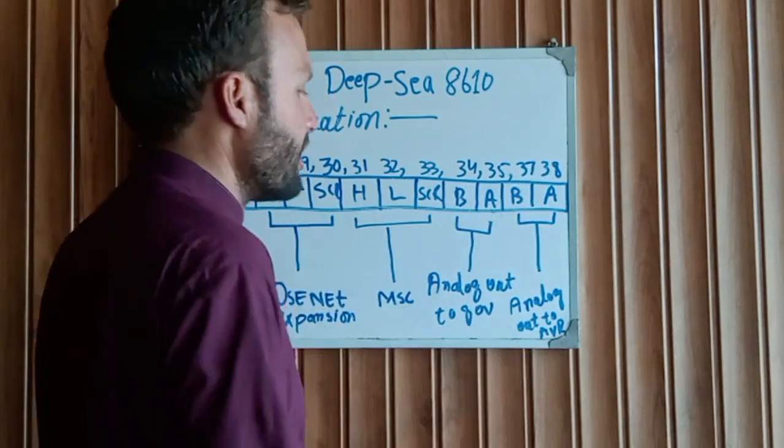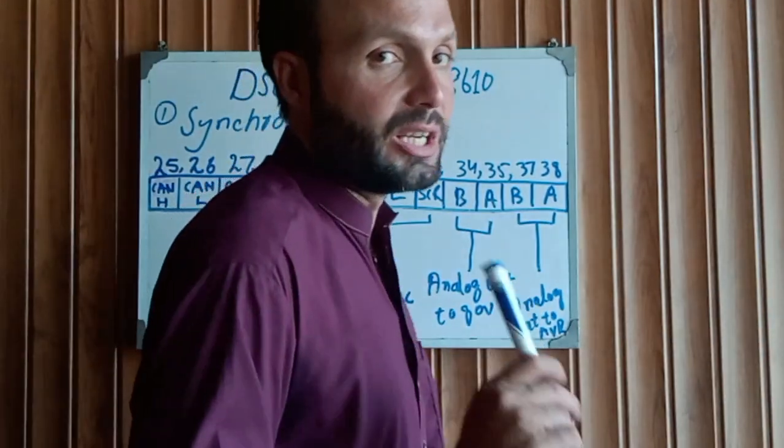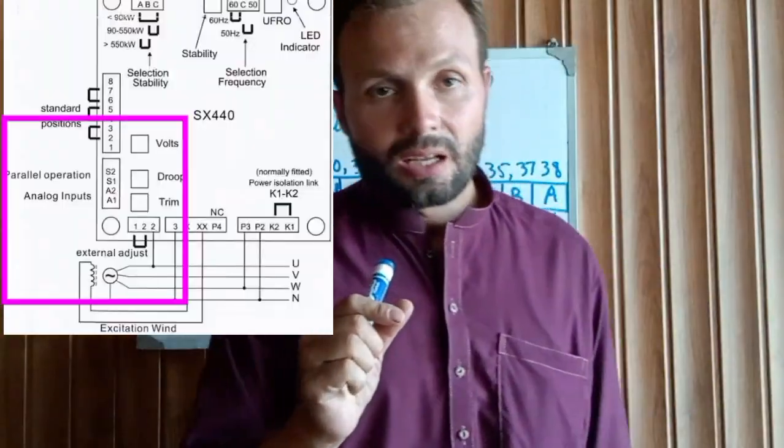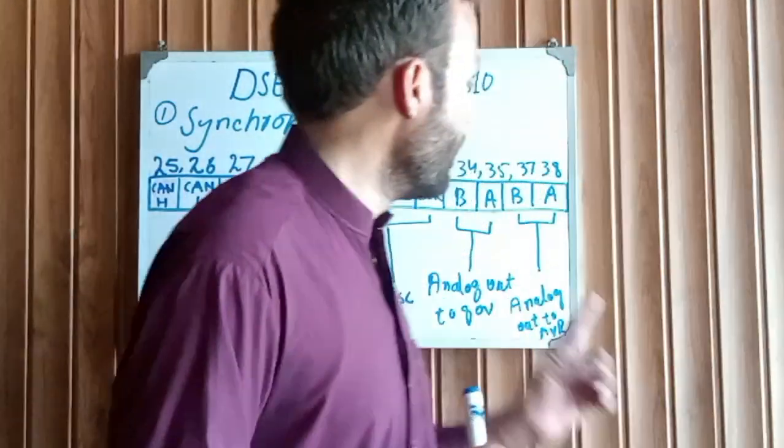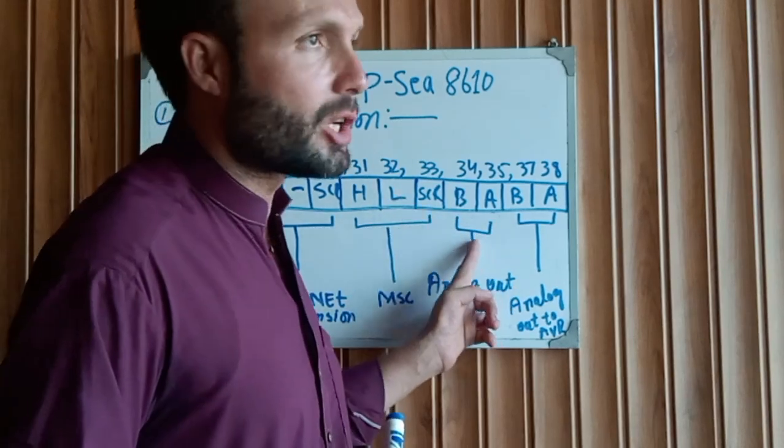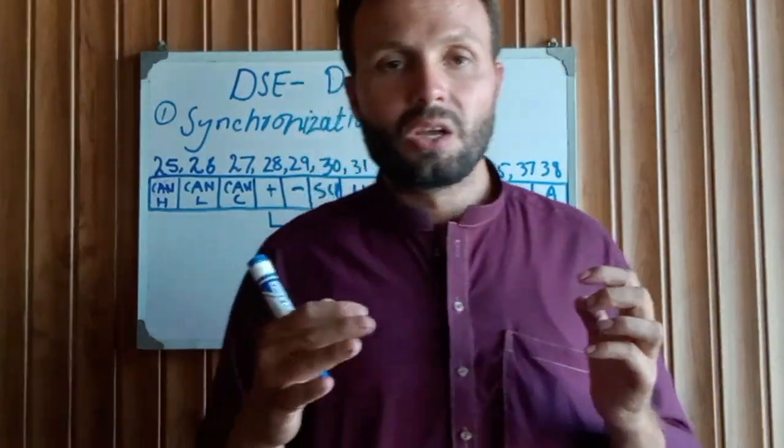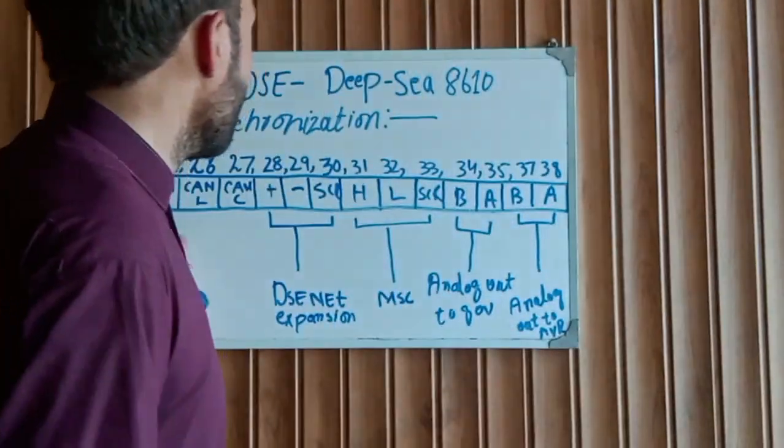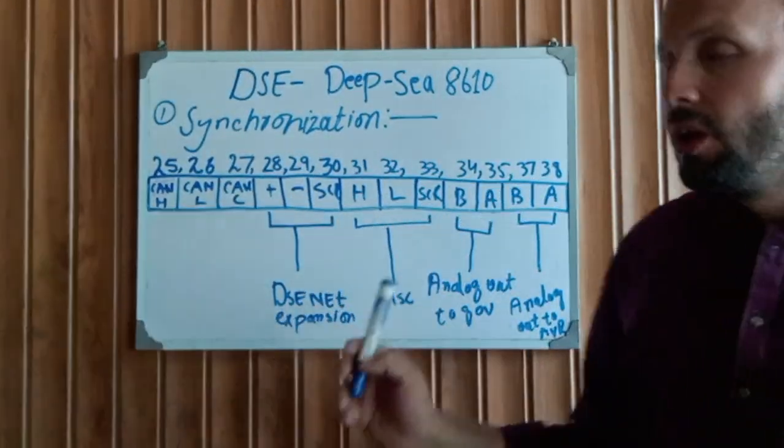Finally, we're reaching the last pin connection, which is more important for synchronization. Pin 37 and pin 38 - analog out to AVR. This is a maximum 5-volt DC output. This 5-volt DC goes to the area where we put the potentiometer to control remotely the voltage stability to increase and decrease the generator voltage. But here, this controller automatically controls the governor system and the AVR system to match all generator voltage and frequency to each other and synchronize all generators. I hope you understand briefly the complete DSE controller wiring and synchronization system.